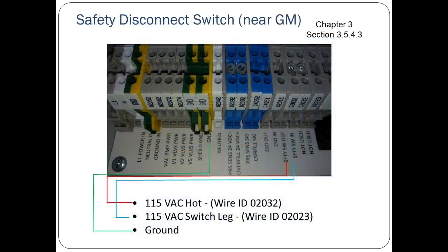Turn to section 3.5.4.3 in the manual for information on the safety disconnect switch. These wires should be pulled out to the gang box, along with the 6 functional wires and pressure sensor cable. The safety disconnect switch wires must be separated from the other wires at the gang box and run to a safety disconnect switch, which is to be installed near the Green Machine.